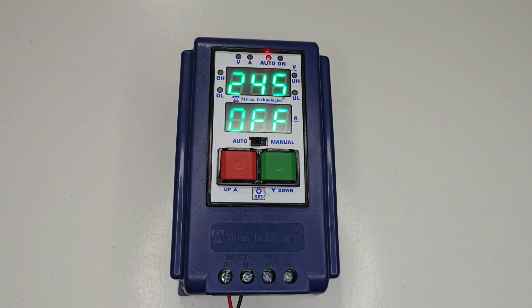Now what is this dry run reset time? Once the motor trips in a dry run condition, after how much time it should start again to check whether it is dry or not. That time is known as the dry run reset time and you can adjust it in minutes.